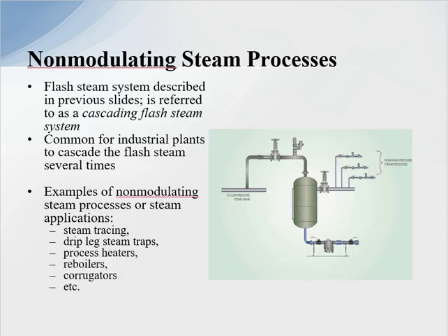This is what we refer to as cascading flash steam — common in industrial plants to cascade flash steam several times from very high pressure down to lower pressure. Some examples of non-modulating steam applications include steam tracing systems, drip leg steam traps, process heaters, reboilers, corrugators, and more. Anytime we have a non-modulating load, we can take it into a flash tank and cascade down to a lower pressure or recover all the flash steam.